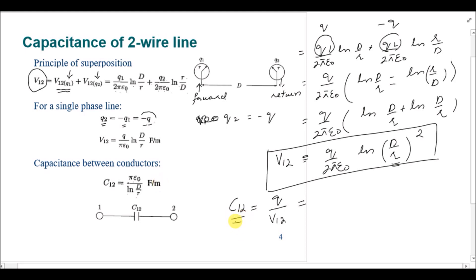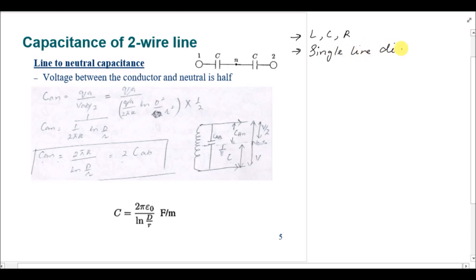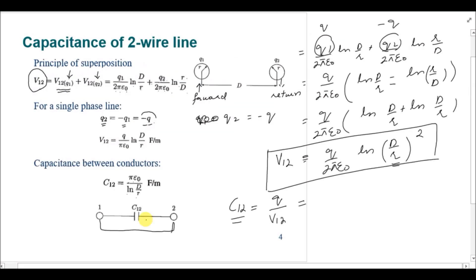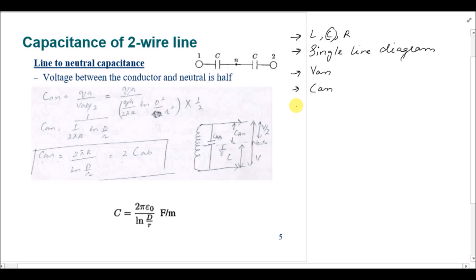This is the line-to-line capacitance between the two conductors. However, when modeling transmission lines, we typically use a single-line diagram with line-to-neutral voltage Van. Therefore, the capacitance value should also be expressed as line-to-neutral capacitance. To convert, we assume the line is supplied by a grounded center-tapped transformer.